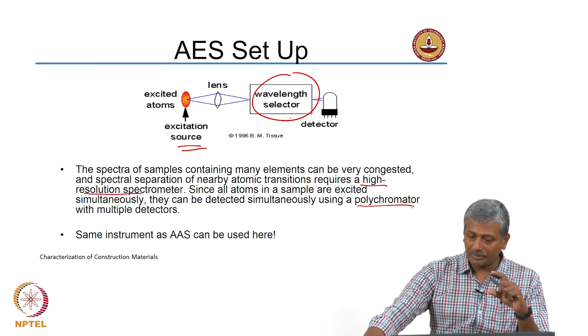So, as I said earlier, the same instrument as atomic absorption can be used here, except that you need to increase the efficiency of the burning system. In atomic absorption we saw that the burning system was essentially a graphite furnace, but when you go to emission spectroscopy you might need to provide better excitation sources. A typical flame, for instance, when you use hydrogen as a fuel and air as an oxidant, produces a temperature of 2000 to 2100 Kelvin.